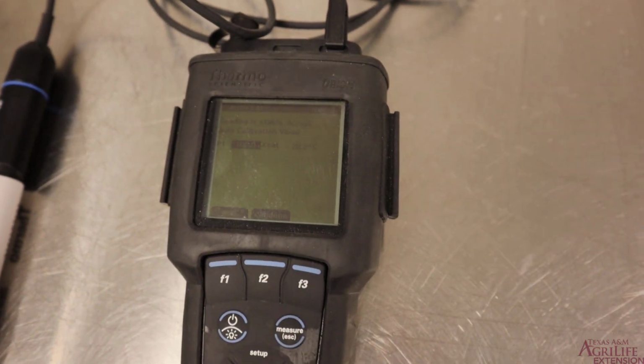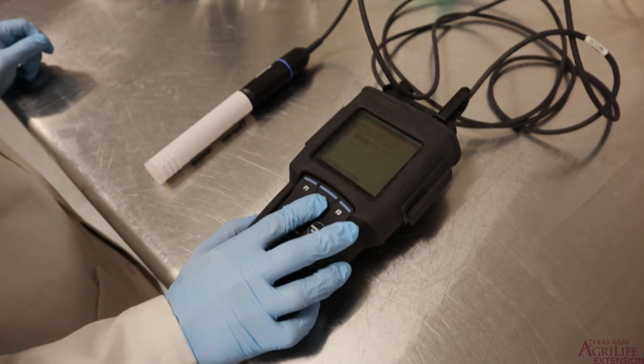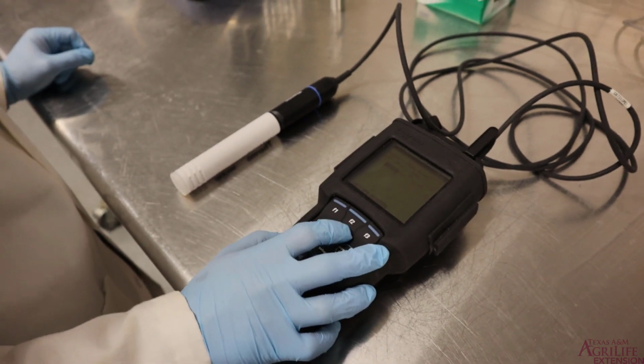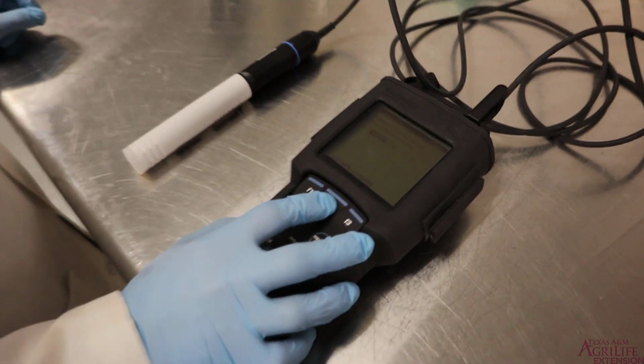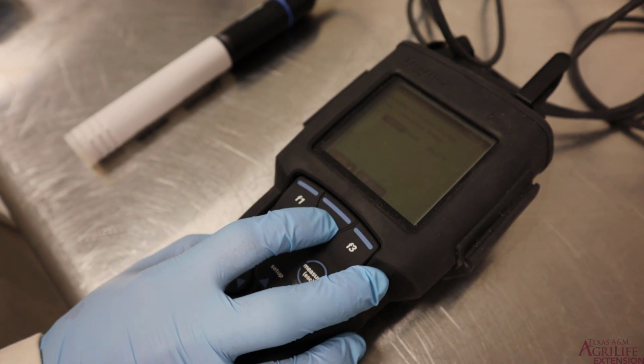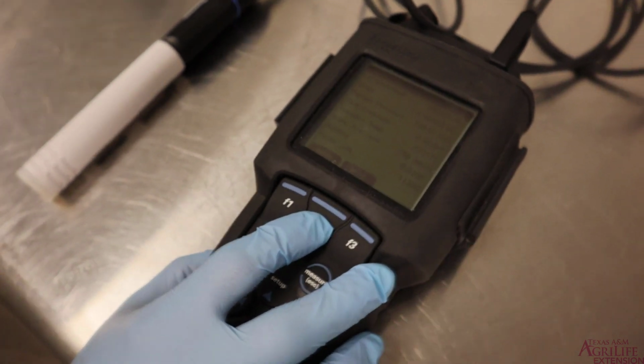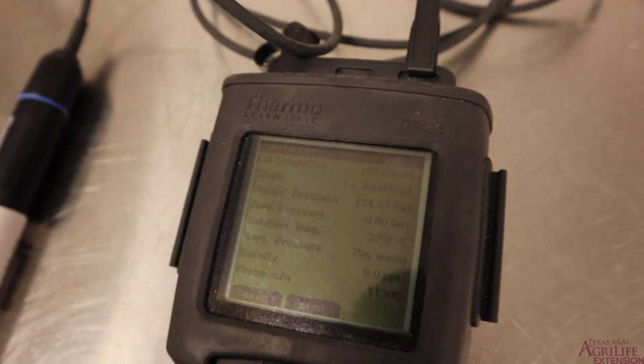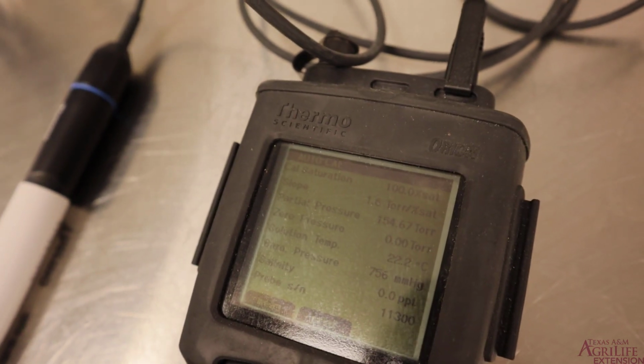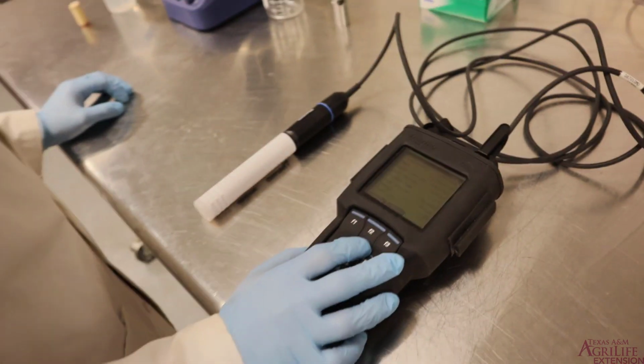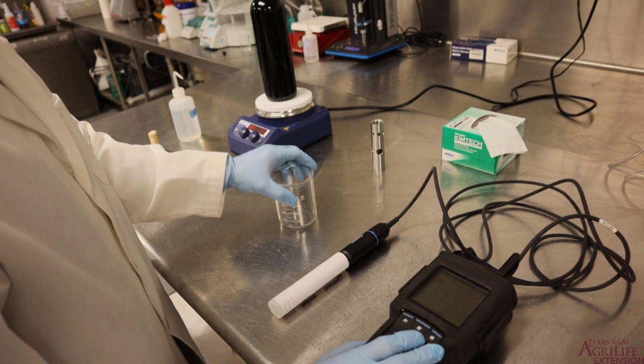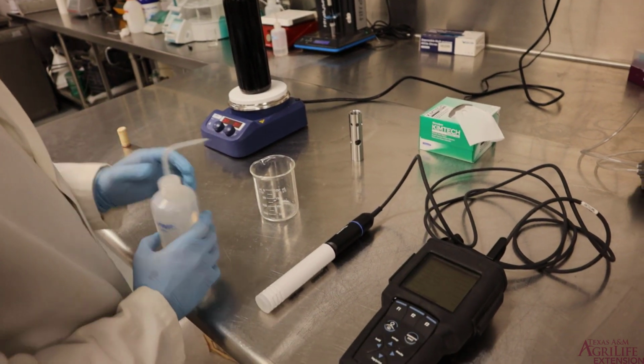Alright, our calibration is complete. It shows 100% saturation, what we're looking for. And to accept this, we'll hit Cal Done, which is F2. It'll take us to a screen where it shows our calibration log of everything that the probe did. It looks good on there. And now we can go ahead and run our measurement.